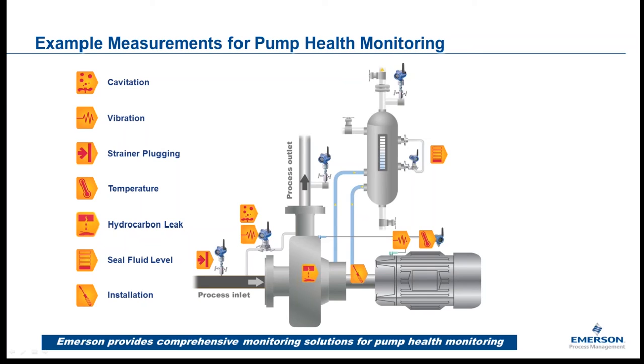Not all pumps have suction strainers, but for those that do, a wireless differential pressure transmitter can replace the locally-reading gauge to signal when the strainer needs cleaning — with that information directed to the maintenance shop. Bearing temperatures and motor winding temperatures can be sensed as leading indicators of problems. Hydrocarbon leak detectors mounted below the pump seal will alert when the area becomes wet with hydrocarbons. Combined with seal fluid level and the vibration transmitter detecting misalignment or installation defects, Emerson provides a fairly comprehensive pump health monitoring solution.